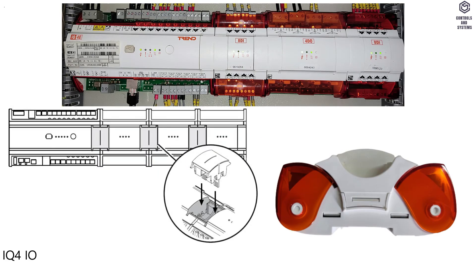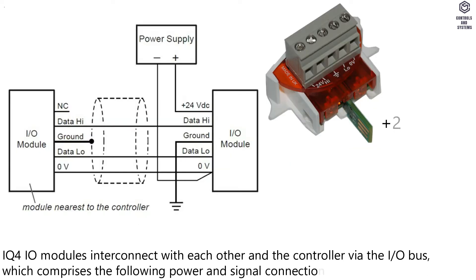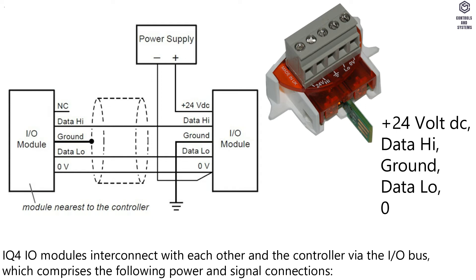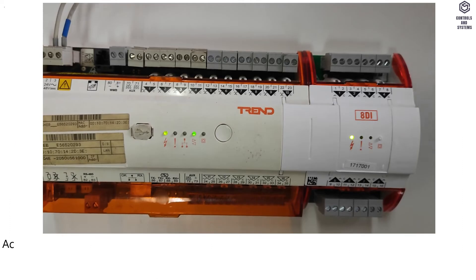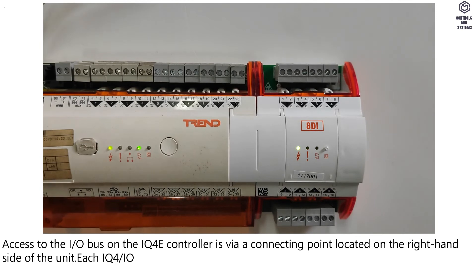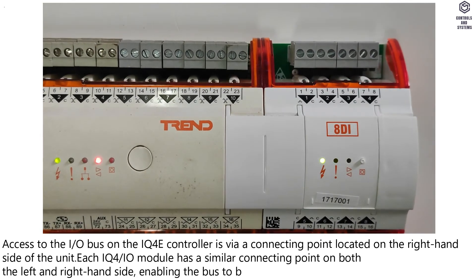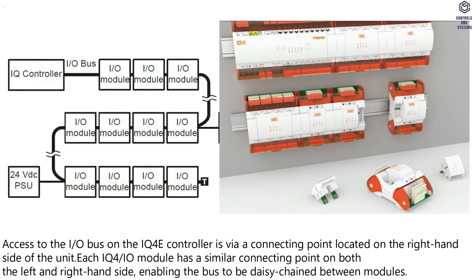IQ4IO modules interconnect with each other and the controller via the I/O bus, which comprises the following power and signal connections: +24V DC, data high, ground, data low, and 0V. Access to the I/O bus on the IQ4E controller is via a connecting point on the right-hand side of the unit. Each IQ4IO module has a similar connecting point on both the left and right-hand side, enabling the bus to be daisy-chained between modules.